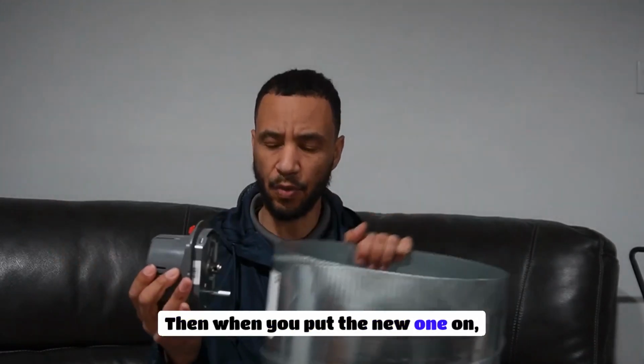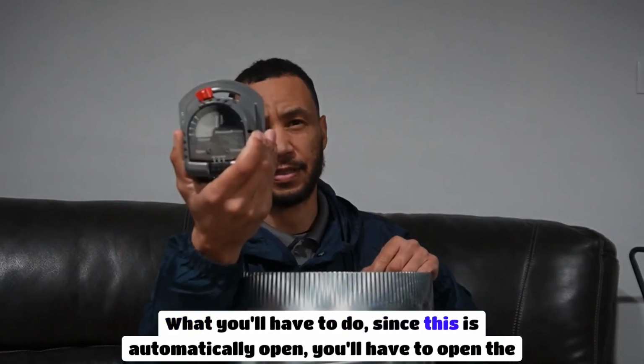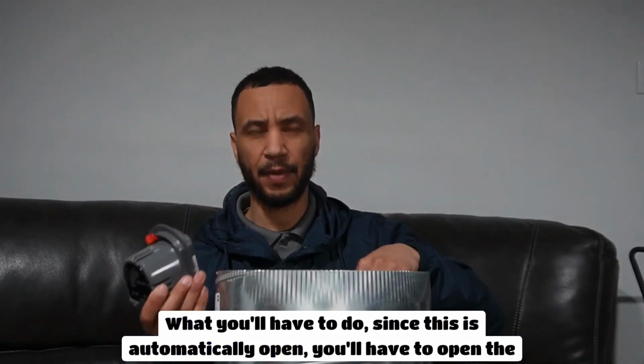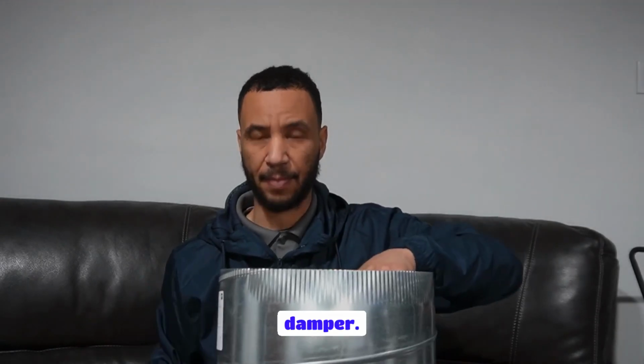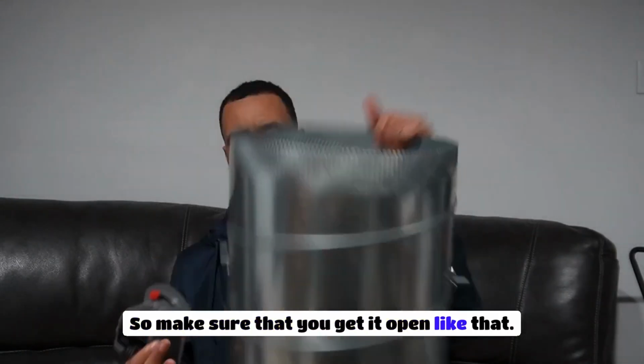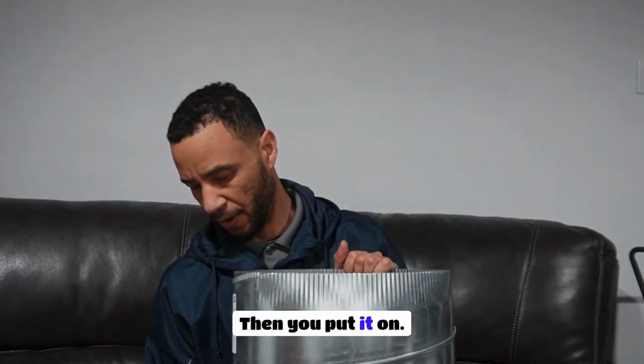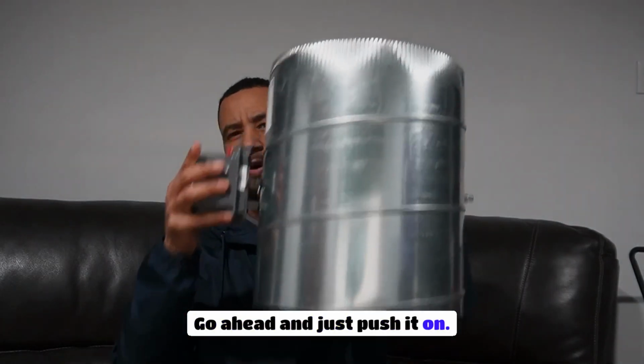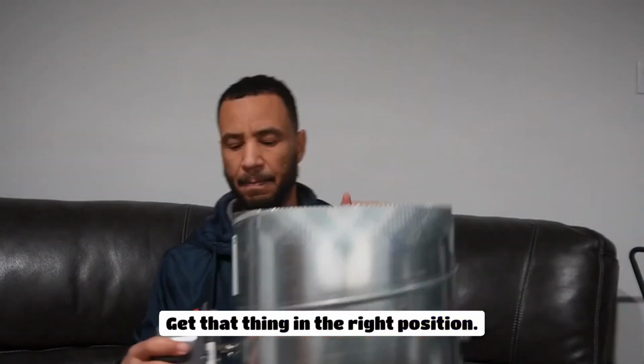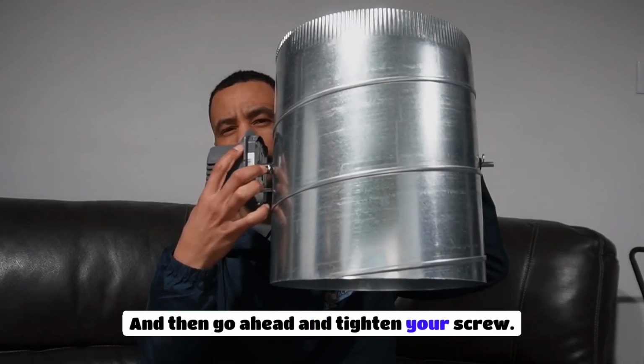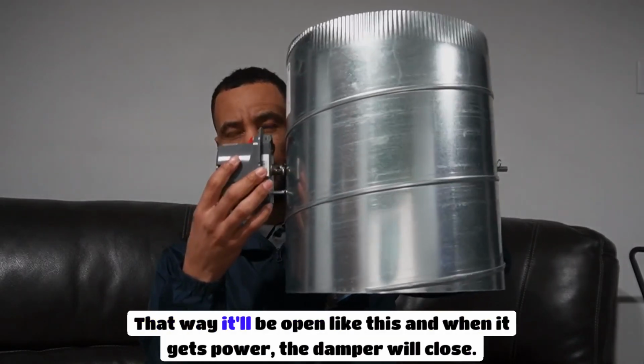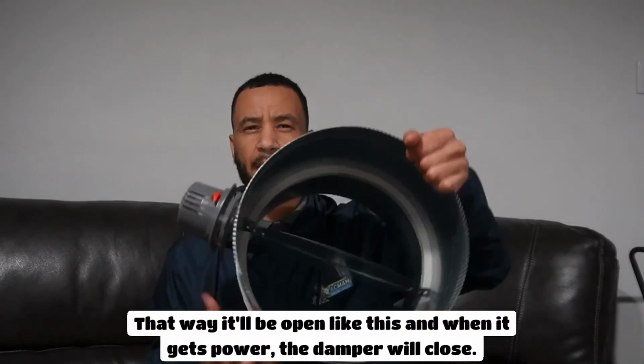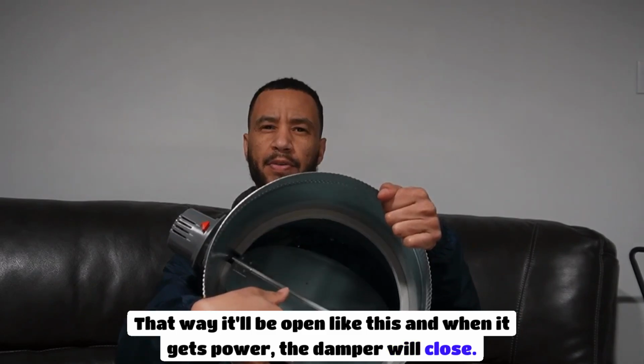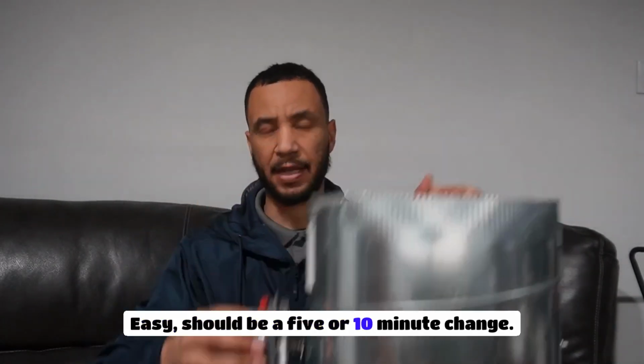Then when you put the new one on, what you'll have to do, since this is automatically open, you'll have to open the damper. Okay, so make sure that you get it open like that. Then you put it on. Go ahead and just push it on. Get that thing in the right position, and then go ahead and tighten your screw. That way, it'll be open like this, and when it gets power, the damper will close it. Easy. Should be a 5 or 10 minute change.